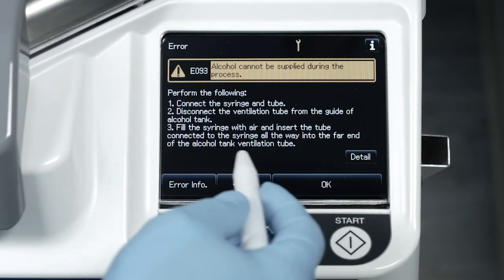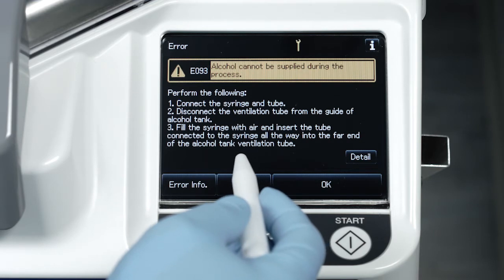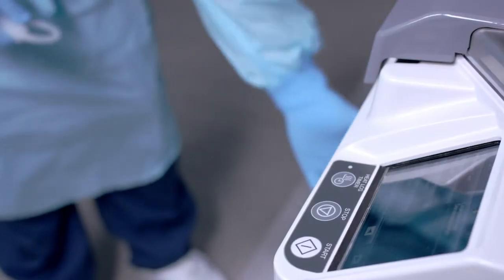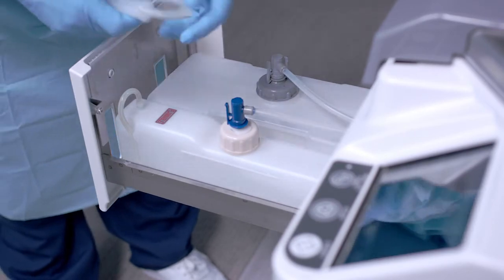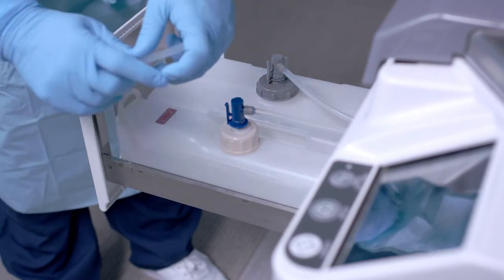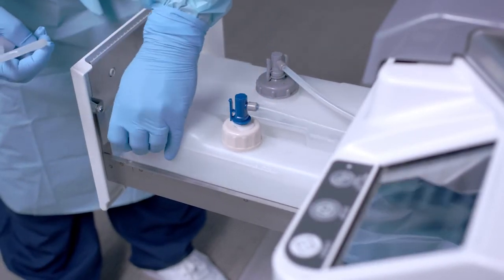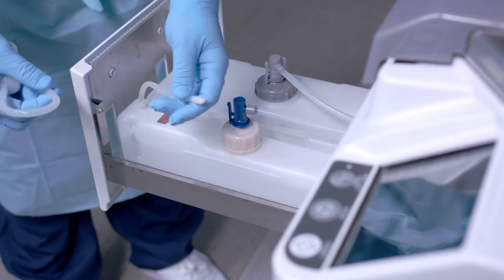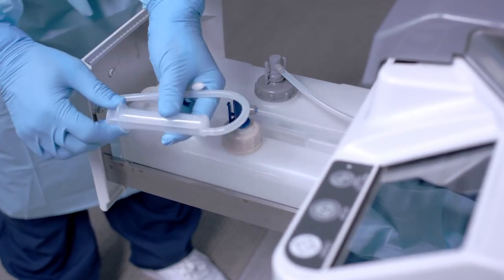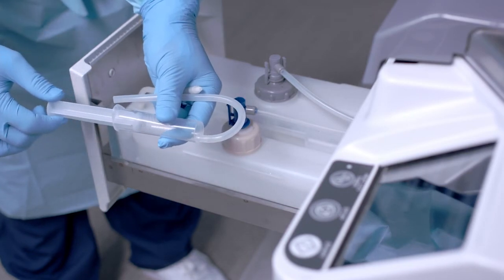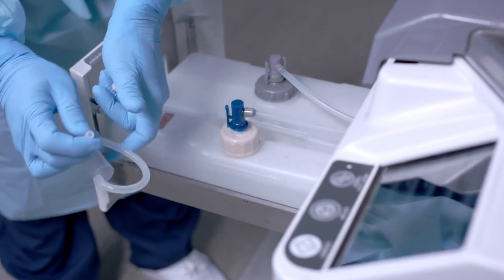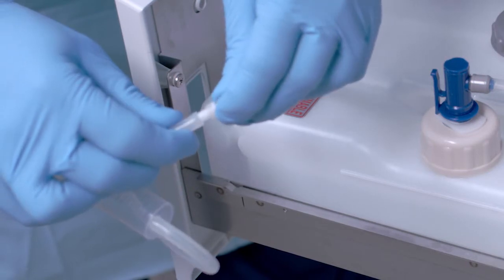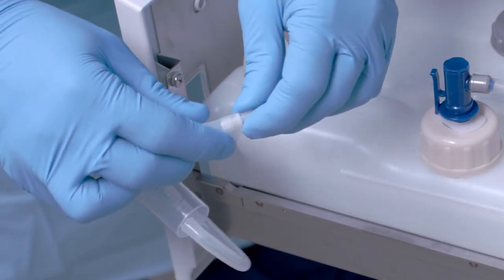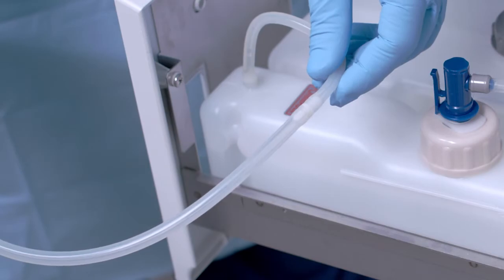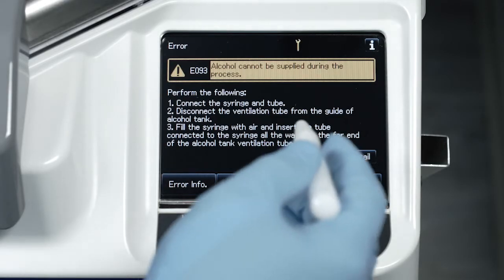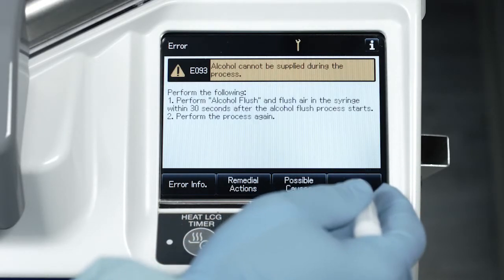Now, follow the troubleshooting steps as outlined on the display. First, connect the provided syringe and tube. Now, disconnect the ventilation tube from the guide on the alcohol tank. Then, fill the syringe with air and insert the tube connected to the syringe all the way into the far end of the alcohol tank ventilation tube. Press OK repeatedly until the error screen is gone.